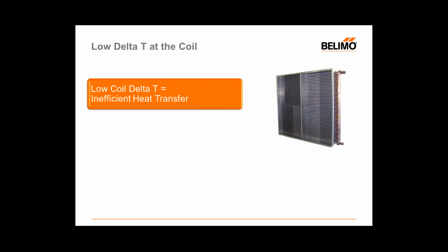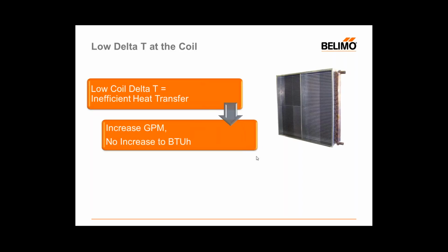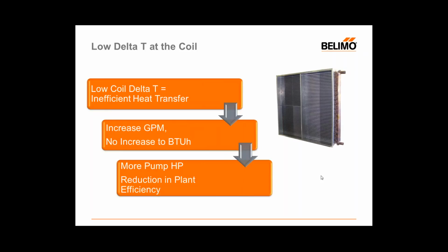Let's start talking about low delta T and what it really means when we sense low delta T at the coil. If we have a low delta T at the coil, it's an indicator that we have an inefficient heat transfer process. And what that really means is we're using more water than we need to satisfy the BTU demand of the load. The other way to look at that is that we've increased our flow rate, but we haven't increased the amount of BTUs that are being exchanged into the space. And when we increase our flow, we obviously create a handful of issues in terms of energy. Most simply, we need to have more pump horsepower used. We need more flow. We're creating more pump heads, so we're taxing the pumps. But we're also going to get a reduction in the efficiency of the plant itself. And so there's a couple of places where we would be concerned about consuming additional energies.